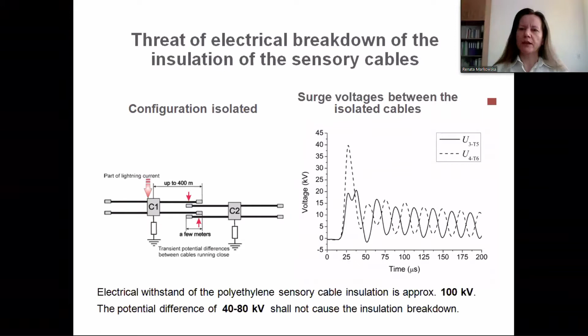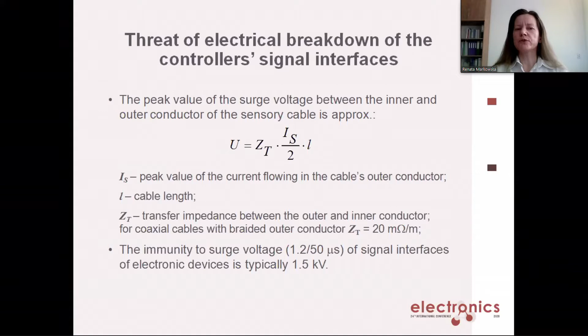Finally, the peak value of the surge voltage between the inner and outer conductors of the sensory cables was estimated approximately based on the peak value of the surge current flowing in the cable's outer conductor, the transfer impedance between the outer and inner conductor, and the cable length. Then the value of voltage was compared to the level of immunity to surge voltage of signal interfaces of the electronic devices.